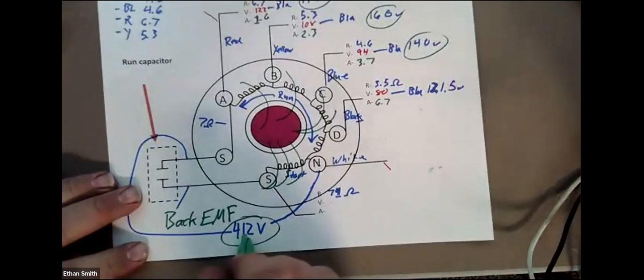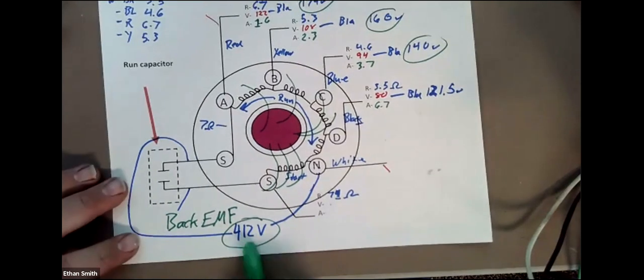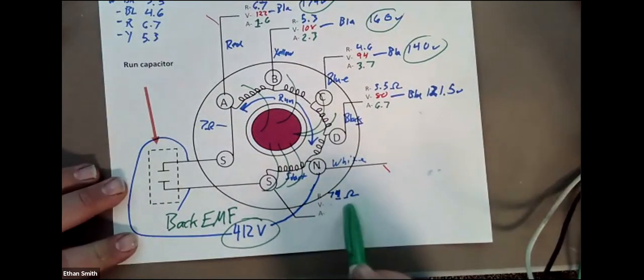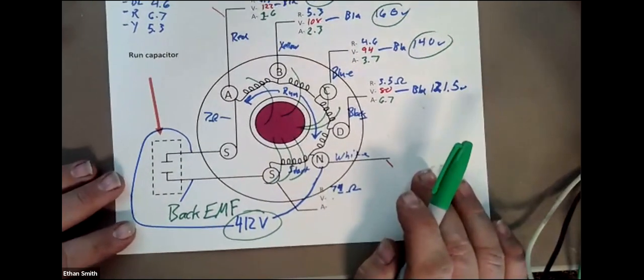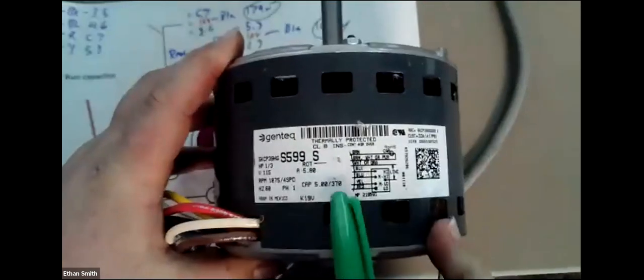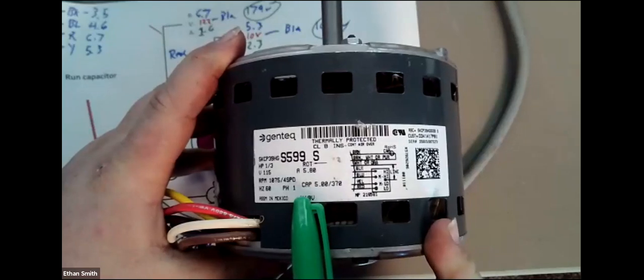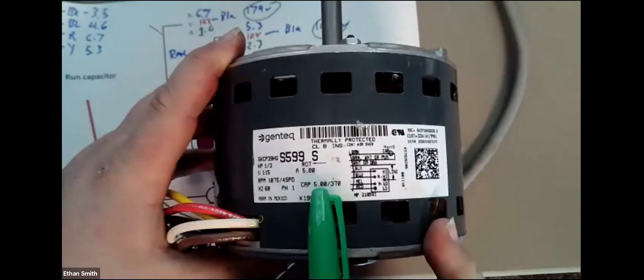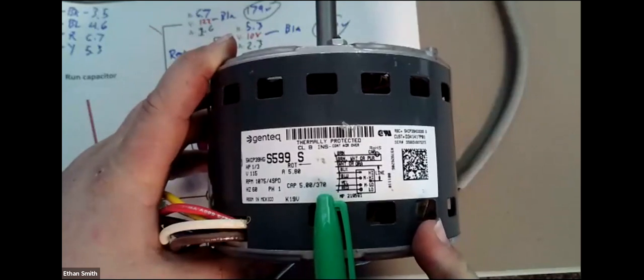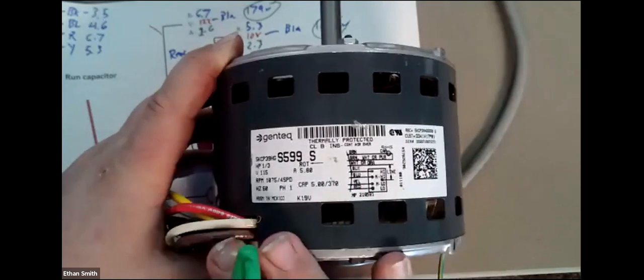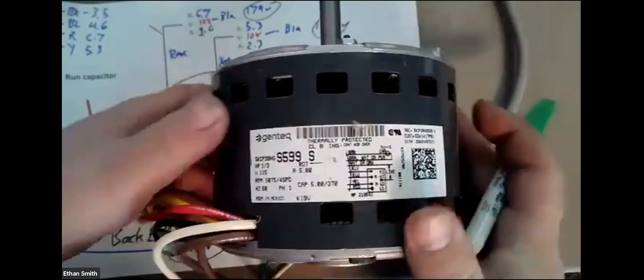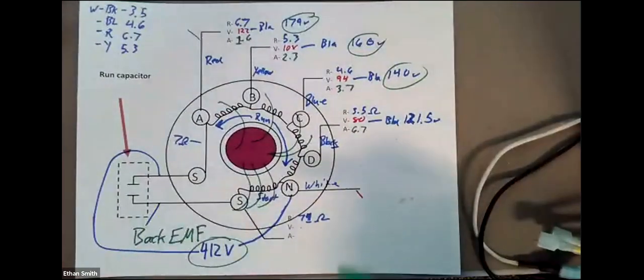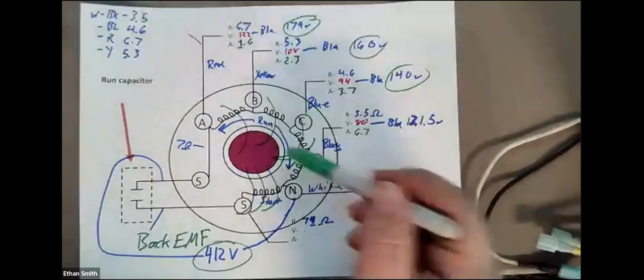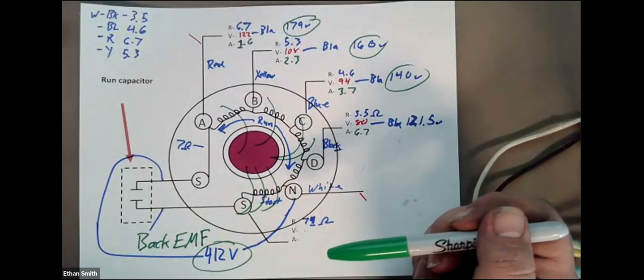And so that's why, when you look at capacitors, the capacitor rating is usually anywhere from 3 to 4 times the standard voltage rating for the motor. If you look at your motors, it'll actually tell you what your capacitor voltage rating should be. So we've got a 5 microfarad capacitor that's supposed to be rated at 370 volts. It's important that you observe that when you're sizing capacitors, because we're going to have this back EMF, and this all runs back to having magnets interacting with coils of wire. Any questions about this, guys?